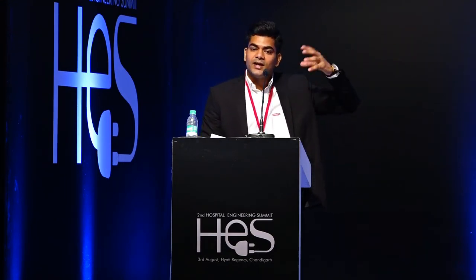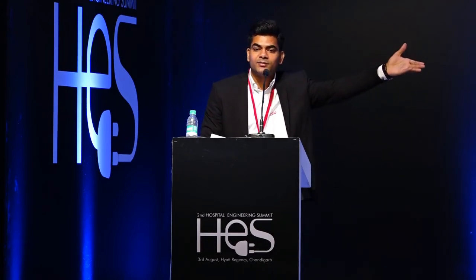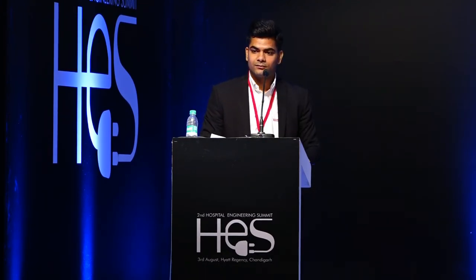A fire door has to be classified by evaluating 3 ratings. One is integrity — fire happens in this room, it should not go to the other room. Insulation means fire happens in this room, but the heat transferred to the other side should be very limited, so that for a particular amount of time it should not ignite anything kept outside. The third is stability — the system should be stable, like a fire door should not fall off after a certain amount of time. That's a big problem otherwise. So those are the 3 things NBC specifies.